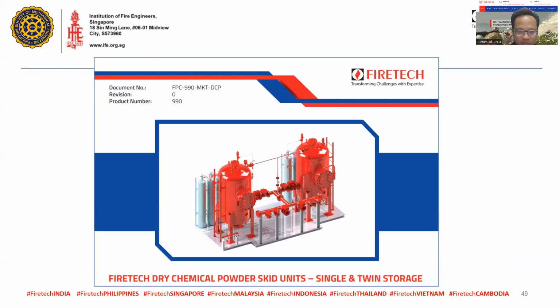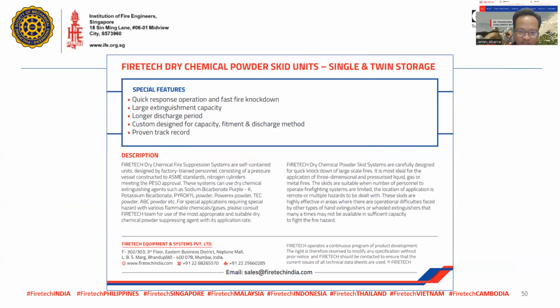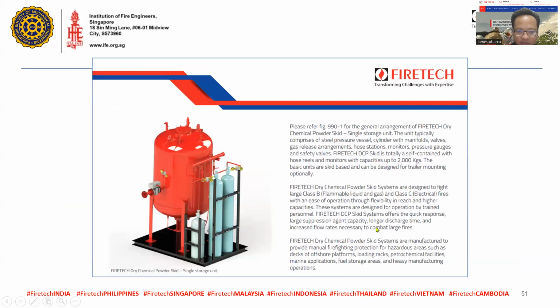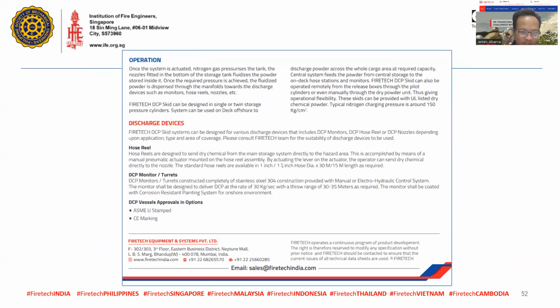And this is the equipment and component that the dry chemical system have. It has tanks, it has nitrogen, it has piping. And these are applicable in hazardous areas such as platform, loading racks, petrochemical facilities, marine applications, fuel storage areas, and heavy manufacturing operations. I installed one of these when I was in Singapore on an LNG tank, the top of LNG tank, and it was very effective. Okay, so we can also produce a tank that has an ASME U stamp or CE marking, and a discharge device for dry chemical. You have your hose reel, you have your monitors as well or turrets, okay, as a discharge device for this.